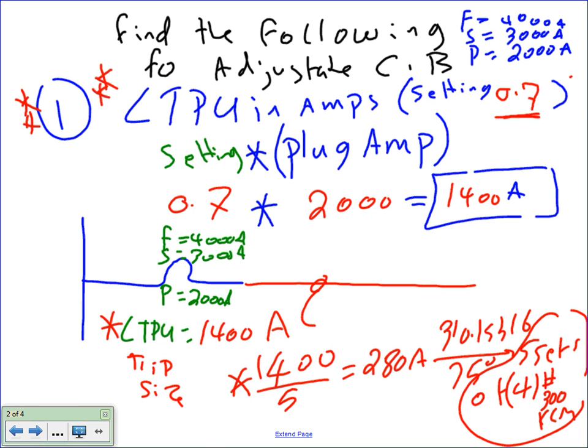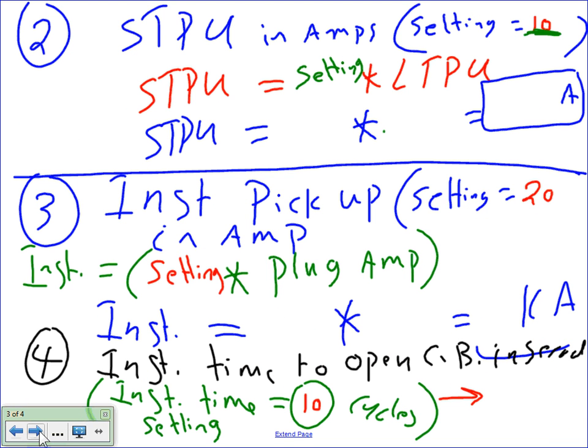The second one, guys, is I'm asking you to find the short time pickup. STPU is industry standard for all the analysis that we do. It's called short time pickup, short time pickup in amps. I decided single-handedly to set this one at 10. I will give you this one on a test. I say the setting is set at 10, and I'm asking you to find the STPU, short time pickup in amps.